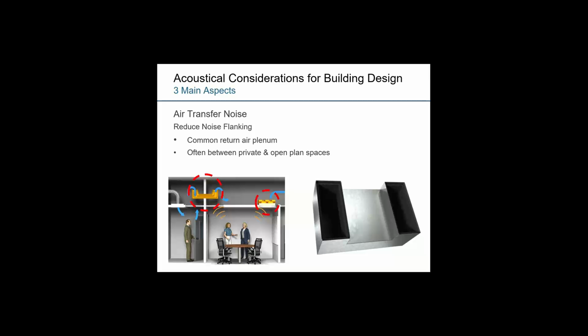When you look at a commercial building, and I'm not sure if you can see on my screen, but above my head, there's a return grill. These are often weak links acoustically within a building design. People will go to great lengths and specify and install high-performing acoustical ceiling tiles, but when there's a large return air grill opening within that ceiling, it lessens the overall ceiling effectiveness, or ceiling attenuation class, we also call it. And installing a return air silencer, such as shown here, above or in conjunction with a return grill, can help mitigate that problem, where your weak link within your ceiling has now been addressed and maybe controlled.